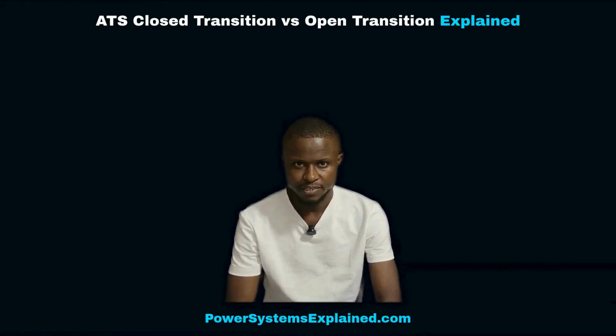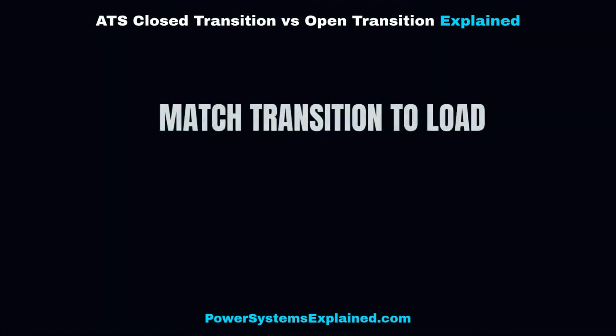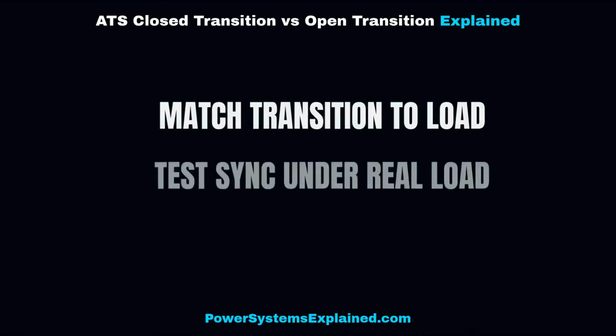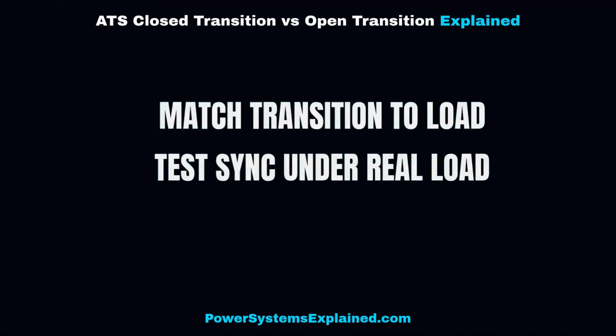Here's what prevents this. Before any ATS goes live on a site, check the motor load, and confirm the transition type matches the load, not just what was convenient. If you are running closed transition, commission the sync settings properly and test them under real load conditions, not just on the bench. If you are running open transition, confirm your transfer time against your most sensitive connected equipment's tolerance and address anything that can't handle the gap. Separate it with something like a UPS.